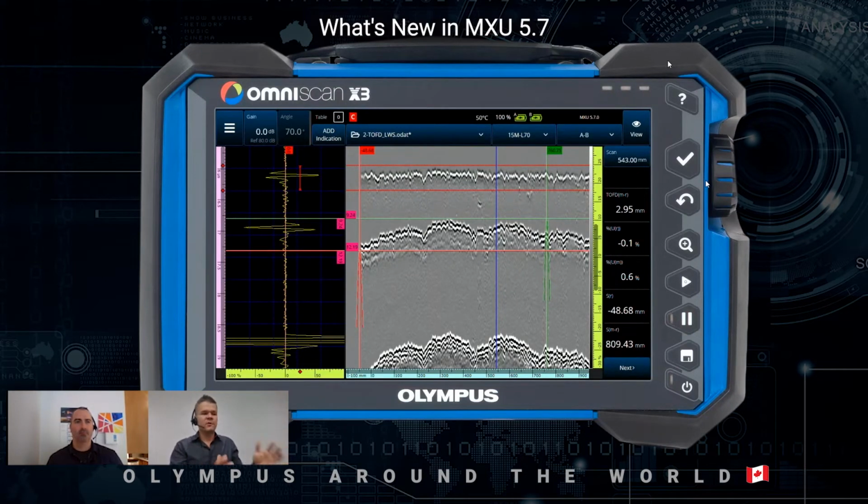Number 2 reason, when you use an X3, the screen is great. It's large, but it's not as large as a WeldSight analysis screen. So cursors tend to be a little bit more in the way of each other. So we figured separating the lateral wave positioning by using the gate would be easier than selecting cursors, than trying to put fingers next to each millimeter, and I can relate. It would just be easier. Yeah, exactly. The bigger your fingers, the tougher it is. So remember gate A? Just bracket that lateral wave with the start and the width.